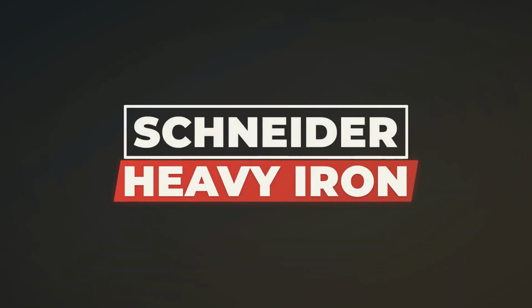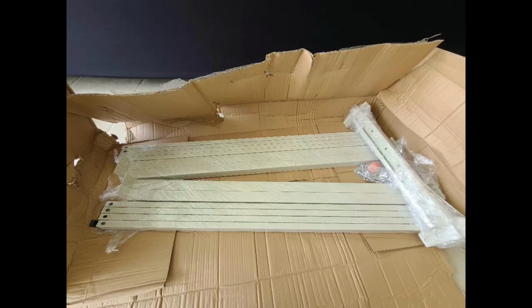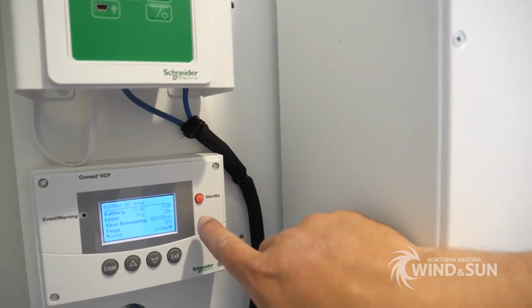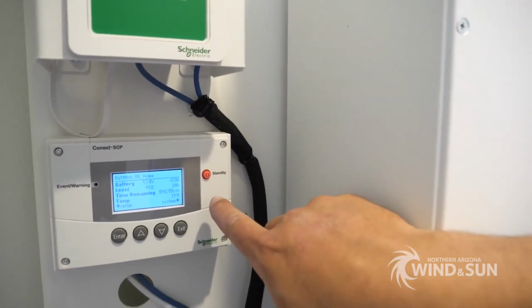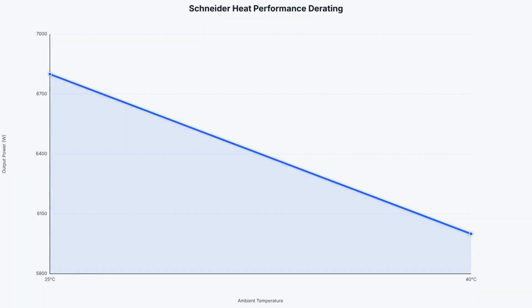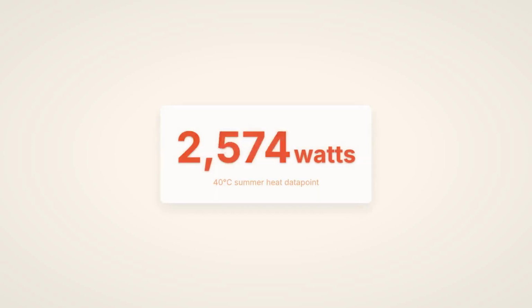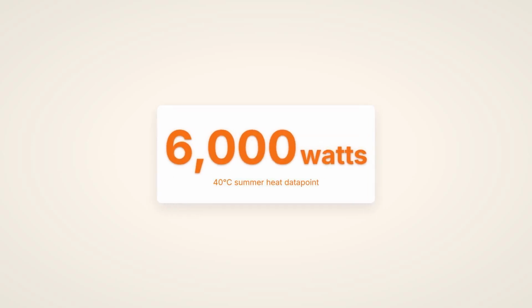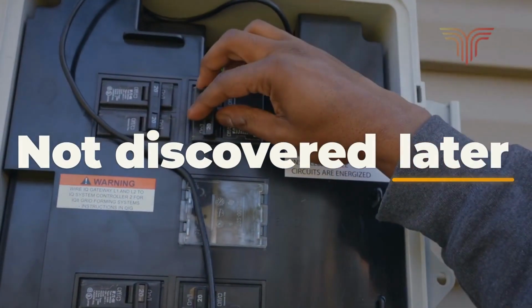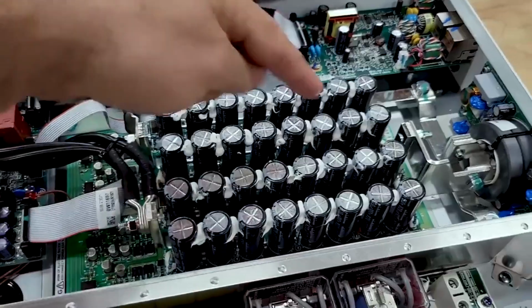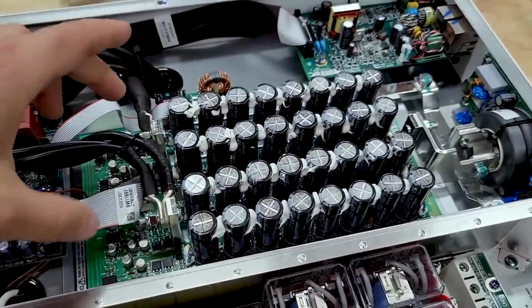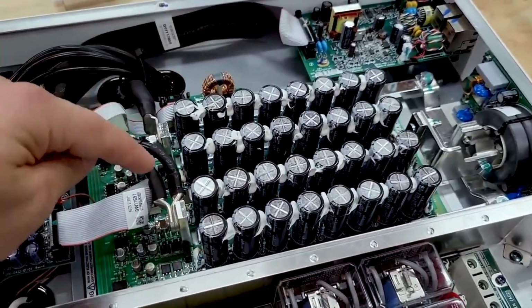It is a transformer-based, heavy iron workhorse built for the kind of loads that make lightweight hybrids flinch. The Conext XW Pro class does something most competitors refuse to do. It publishes output at temperature, rated at 6,800 watts at 25 degrees Celsius, dropping to roughly 6,000 watts at 40 degrees. That is an 800-watt penalty written directly into the datasheet, not discovered by a frustrated installer in August. That transparency alone separates Schneider from half the brands that quietly derate in summer and say nothing about it.